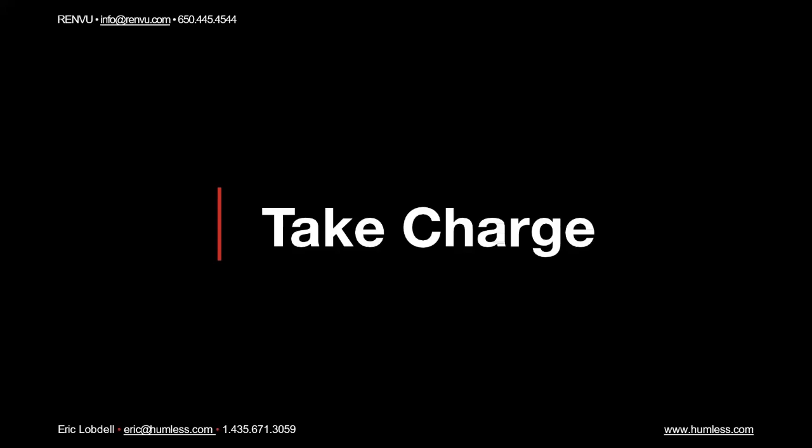The real world of lithium is, right now, nobody knows really. I mean, there's no lithium system that's been in place for more than 25 years yet, and there's a lot of talk about 30-year systems. We know the 10-year warranty is solid. We know the 4,000 cycle is solid. It's the little things, the little parts, the MOSFETs, that will eventually wear out. Depending on depth of discharge, you could get 6,000 cycles. You could go 12, 14 years, depending on how you DOD it. But at 10 years, we're expecting the battery to still be doing 80% performance of its original capacity.